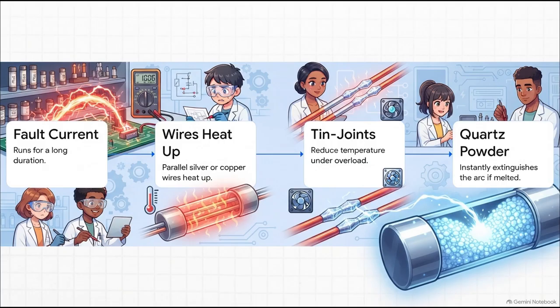and they're perfectly tuned so that only one wire melts at a time. To keep things from getting dangerously hot under overload, they use special tin joints that literally help reduce the temperature. But if the fault keeps going and isn't cleared, the element finally melts, popping the circuit open. And here is the absolute genius part. The inside of that enclosure is packed full of powdered, pure quartz. The exact split second that wire melts, that pure quartz acts as an instant extinction medium, completely smothering the arc.